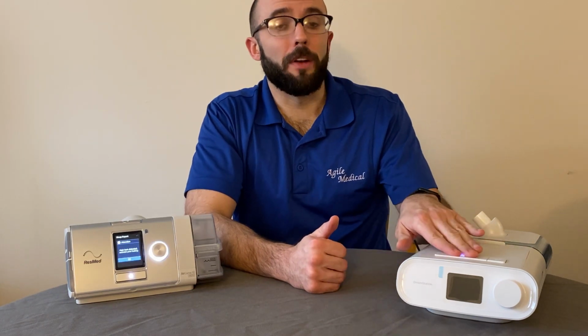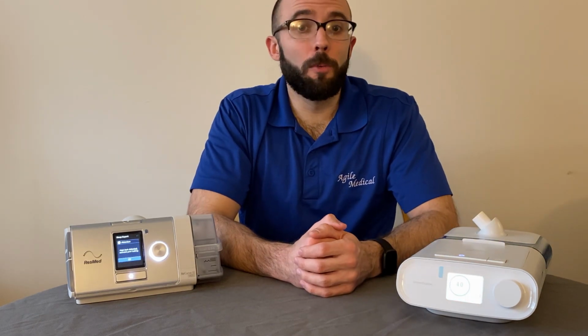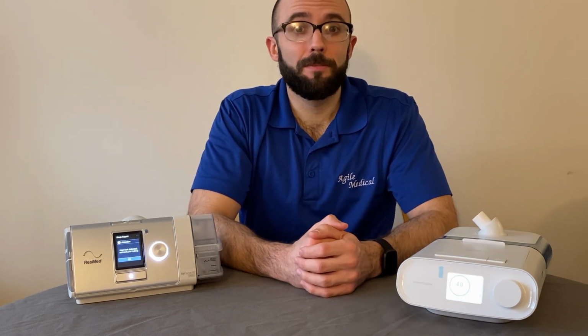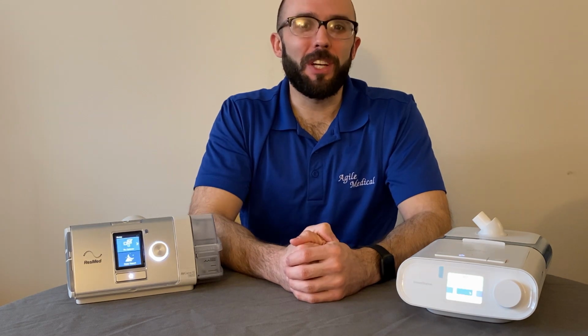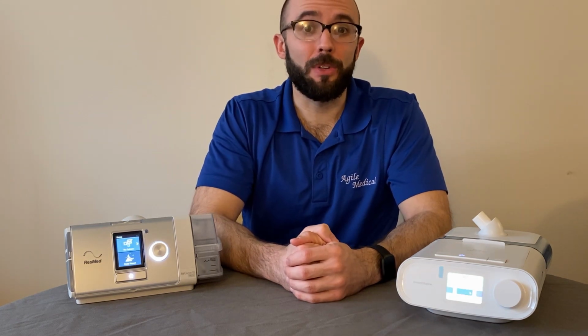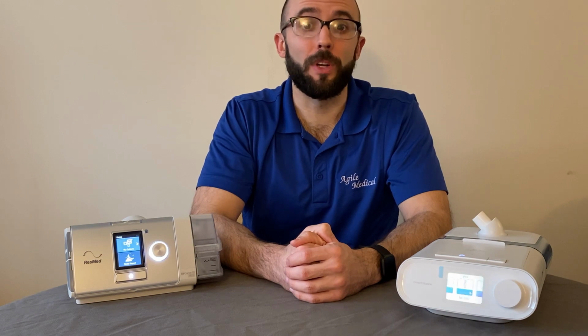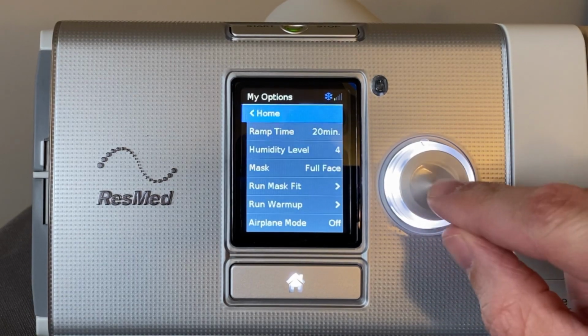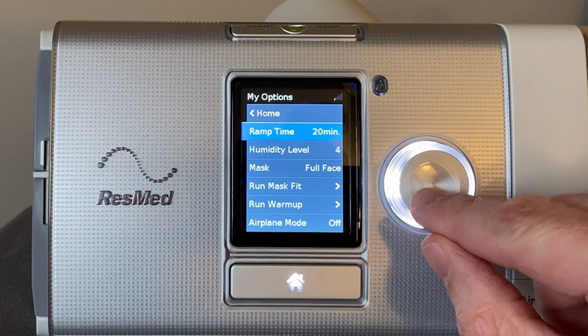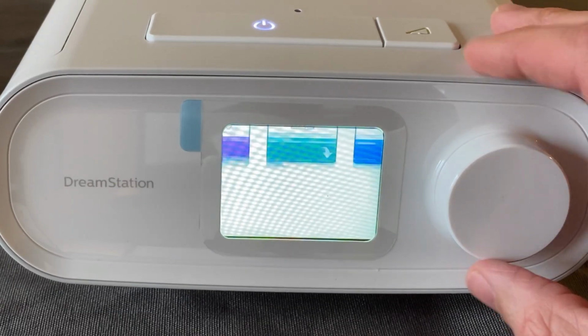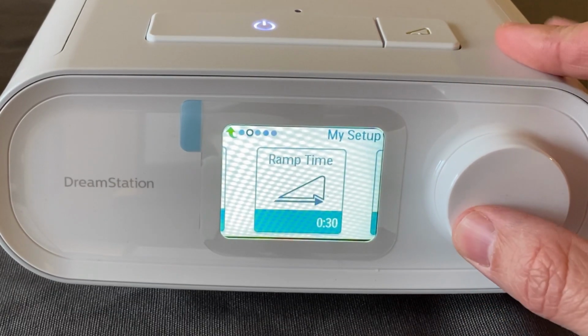If you're familiar with the DreamStation Auto or AirSense 10 Auto CPAP units, then the functionality of their BiPAP counterparts is pretty similar. To begin therapy, make sure the device is plugged into a known working outlet and press the start button. The motor will begin and air will begin to flow through the tubing to the mask. Much like an auto-adjusting CPAP, these units are designed to increase or decrease air pressure throughout the night according to your needs. Both units provide patients with a ramp feature, the settings for which can be accessed through the My Options menu on the AirCurve and the My Setup menu on the DreamStation.